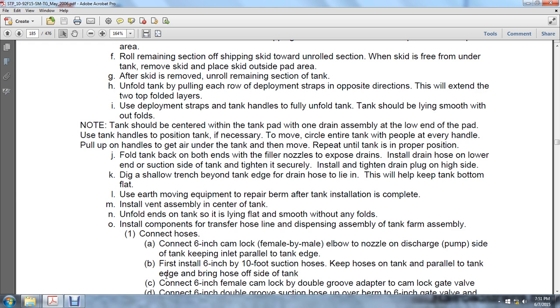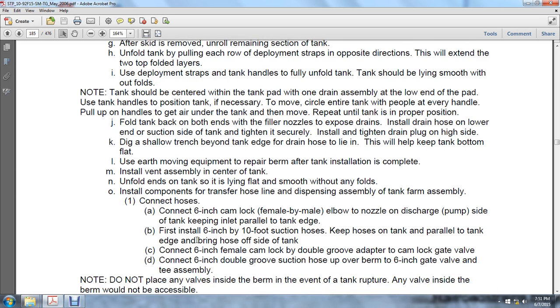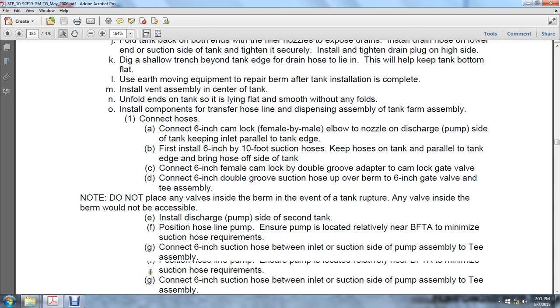First, install the 6-inch suction hose. Keep the hose parallel to the tank at the edge of the tank, bringing the hose to the offside of the tank. Connect the 6-inch female cam lock with a double grooved adapter for the cam lock valve. Connect the 6-inch double groove suction hose over the 6-inch gate valve of the assembly. Do not place any valves inside the berm in the event of a tank rupture. Any valve inside the berm would not be accessible.